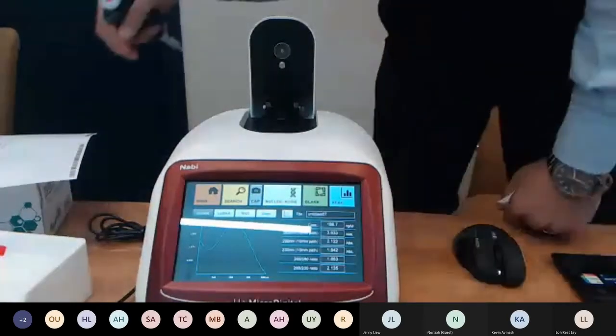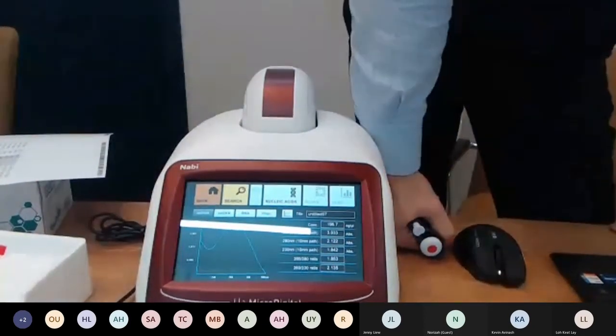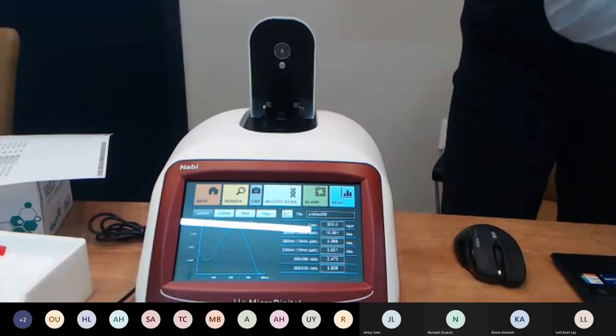Let's move on to what should be 600 ng/µL — which we measured this morning at around 675. If you dilute a DNA sample and leave it out for around 12 hours, the concentration goes up due to evaporation. If the result and ratios look wrong — for example 260/230 around 2.47 and 3.84 — this usually indicates an issue with pipetting. The key problem is that you need to get the sample onto the small hole in the center of the column where the light passes through — if you miss it, the results will be off.